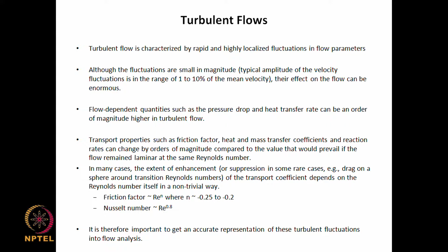And similarly, if you underestimate the friction factor, assuming it to be laminar flow, then the pump that you require to maintain flow through a particular pipe at a particular Reynolds number can be small by an order of magnitude. You probably would have required a 10 horsepower pump, and you bought only a 1 horsepower pump, because that is what you estimated. So you can grossly over design or under design your heat transfer or fluid flow equipment if you neglect the fact of turbulent flow. Okay.